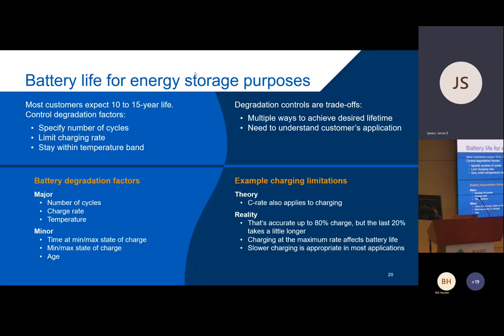So what impacts the life for these batteries? Most customers with lithium are expecting not 5-year life, but 10 to 15-year life. So how do you control the degradation of that battery? Well, you do want to have some limit on the number of cycles. 5,000 a year would be too high, for example. I also want to limit charging rate.